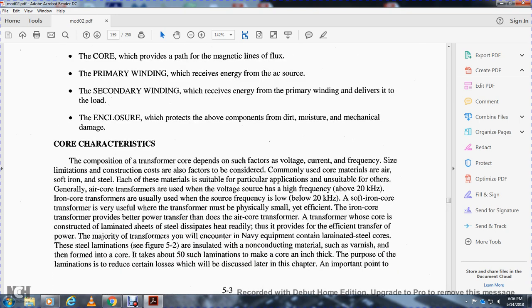Core characteristics: the composition of the transformer core depends on factors such as voltage, current, and frequency, as well as construction limitations. Commonly used core materials are air, soft iron, and steel, each suitable for particular applications. Air core transformers are used with voltage sources of high frequencies above 20 kHz, while iron core transformers are used with source frequencies below 20 kHz. Soft iron core transformers may be physically small yet efficient; the iron core transformer provides better power transfer than the air core transformer.